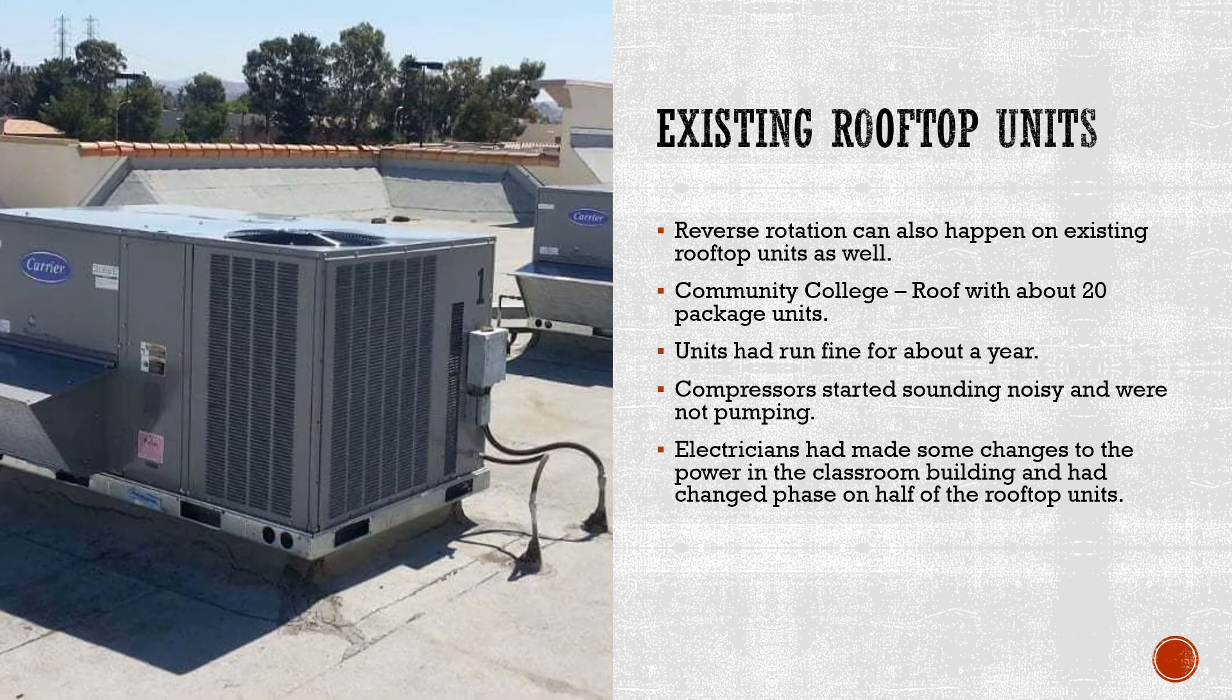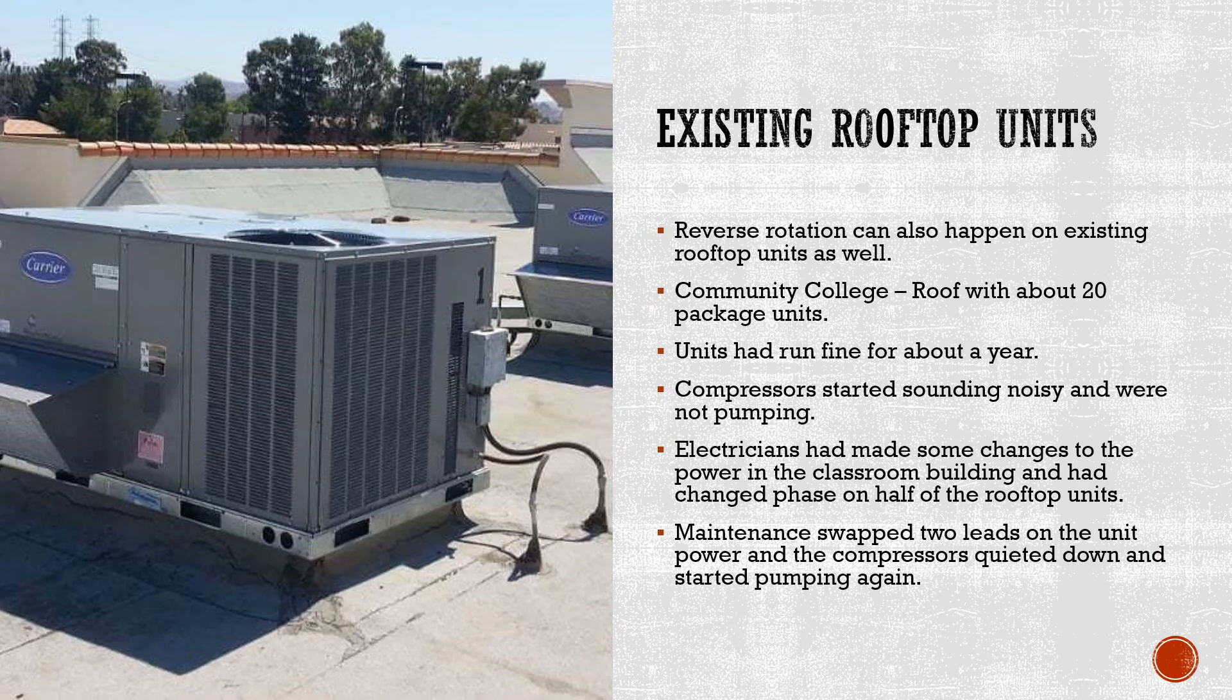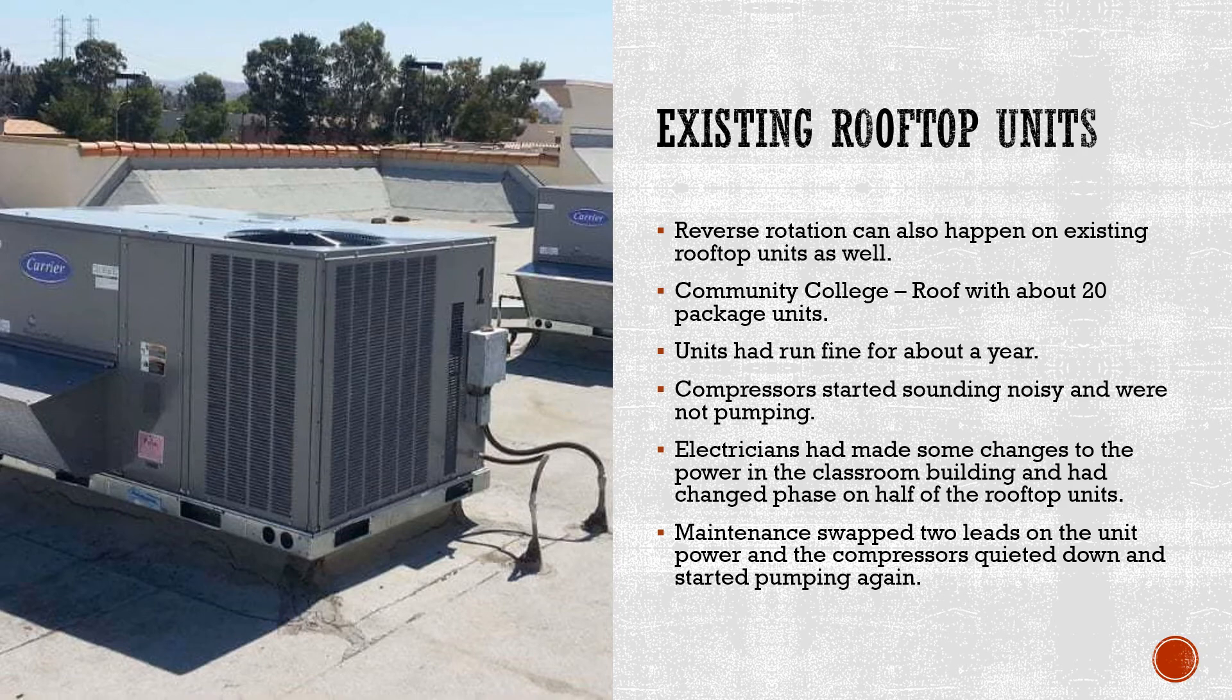Electricians had made some changes to the power in the classroom building and had changed phase on half of the rooftop units. Maintenance swapped two leads on the unit power, and the compressors quieted down and started pumping again.